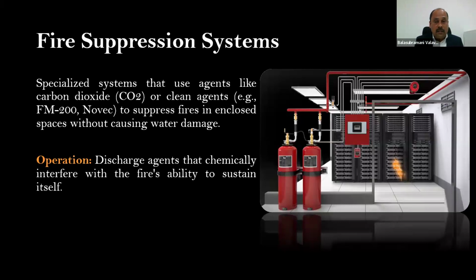The other greatest advantage of this particular system is, once the fire is put out, within 30-40 minutes you can go and work. You will not have any evidence of fire except in the area where the fire happened. One more important point is that you can save the data. If you pour water on the equipment, you will not be able to use it. But in this case, with this particular gas, you can put out the fire, retrieve the data, and use it again. No damage will happen to the data.